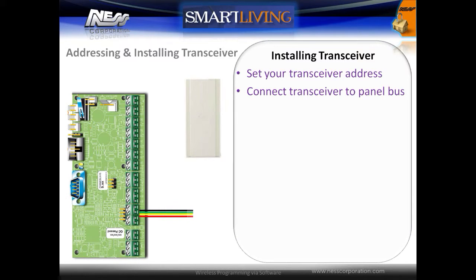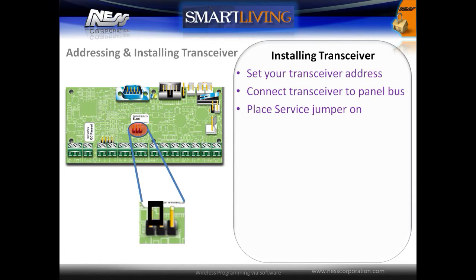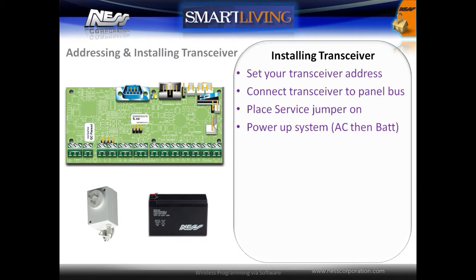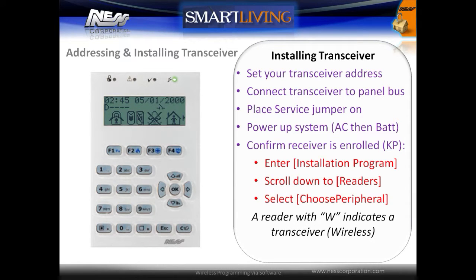To install a transceiver, first set the address on the transceiver and connect to the system's bus. Next, place the system into service mode so the transceiver can be automatically enrolled. Power up the system, first applying AC power and then connecting the battery. Then confirm the receiver is enrolled by going into the keypad's installation programming menu, scrolling down to readers and then selecting choose peripheral. A reader with a W indicates a wireless transceiver.